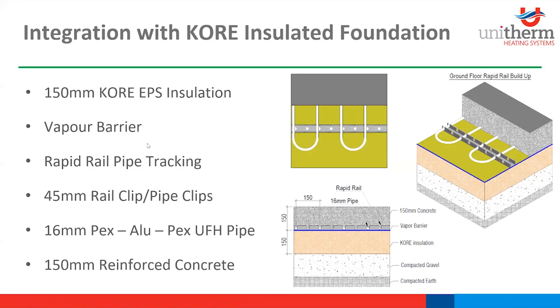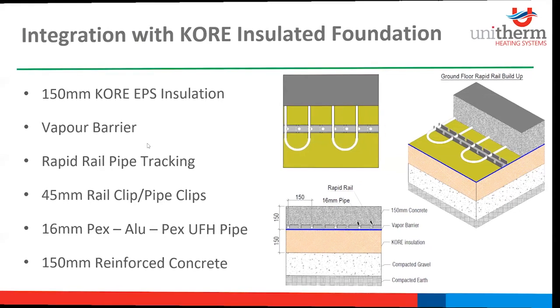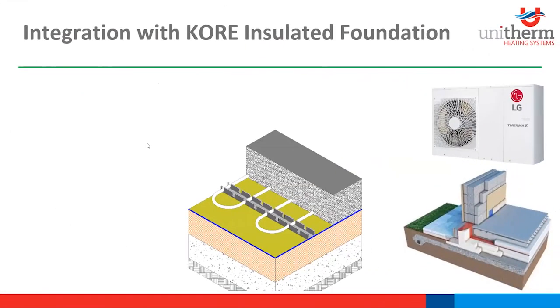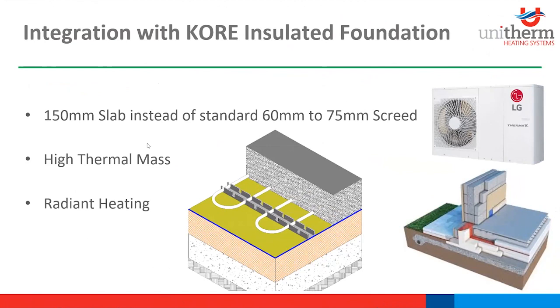Obviously we have twice the amount of heated screed or heated slab as we would normally have now, compared to a 75 mil screed. I'll talk to you a bit further about that. As mentioned previously, for a 75 mil screed, the method of heat transfer from the heated floor is about 55% radiation and the other 45% convection. With a 150 mil slab instead of a 75 mil slab, we've now doubled the thermal mass in the floor, therefore significantly increasing the longevity of radiation from the floor. Because the majority of the heat is now predominantly radiant, it creates occupant thermal comfort at even lower air temperatures.